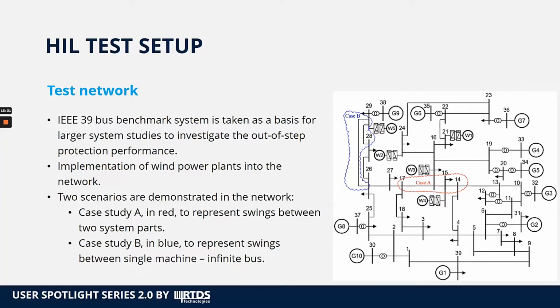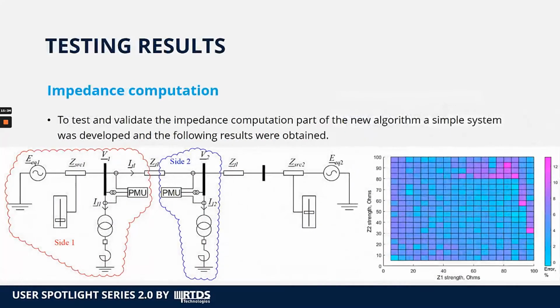Moving on to testing results. As the impedance computation part of this algorithm is essential for the algorithm's operation, the accuracy of this part of the algorithm had to be tested. So in order to test and validate the impedance computation part of the new algorithm, a simple 2-machine equivalent system was built with adjustable source impedances at either side of the network.